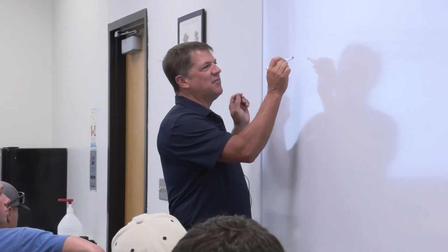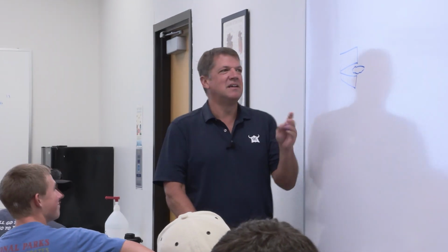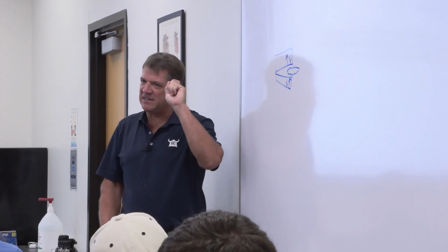Jonah and Jordan, inside the hospital, you go in and you just stick the pulse ox on them. It's just a little clamp device that goes on their finger. And if I can draw that clamp device, I'm going to do it very crudely here. It kind of hinges and it goes on the finger, and her fingernail's under here, okay? You kind of with me on that? Looks like a Pac-Man, doesn't it? So what's happening is there is a transmitter here and a transmitter here, and there's also a receiver here and a receiver here. The transmitter is shining both visible red and infrared light.